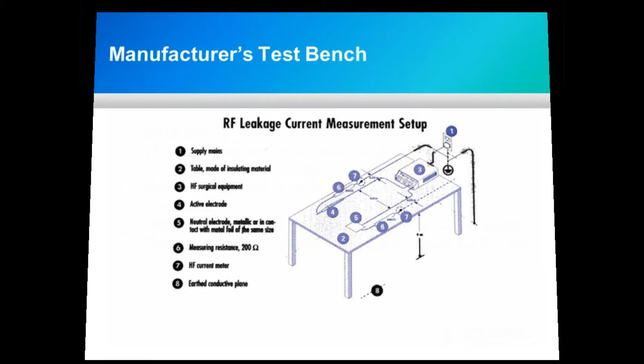Why test for it besides patient safety? This is just an example. In one study, 31 insurance agency companies provided data from 615 claims, of which the major claims were not directly associated with procedures. The thermal damage was due to unintended patient tissue damage. So there is proof out there that there is damage from this. What kind of problems? As leakage increases, the density surrounding the patient tissue increases, at both the active electrode and the dispersive electrode. When the thermal density increases, the tissue can suffer unnecessary damage. So instead of having just the regular surgical site, you'll have more damage beyond the surgical site.